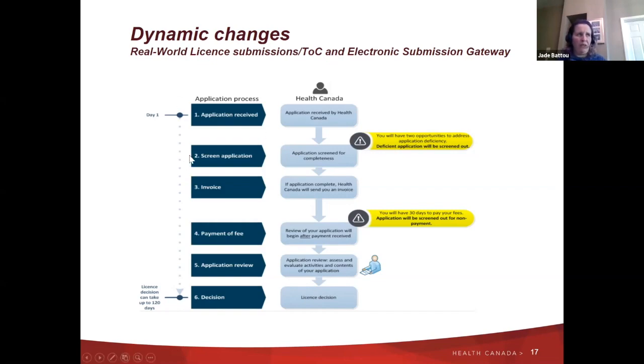Once we receive the application, it goes to regulatory screening to make sure we have the quality management certificate, the application form, and the device label. When we find the file complete from a regulatory perspective, we move it to scientific review for class 3 and 4 devices. However, for class 2, unless requested by the scientific division, we don't move them to scientific review because they're considered low risk devices.